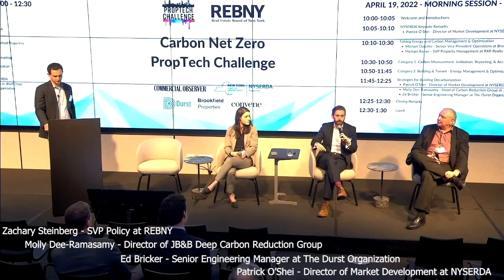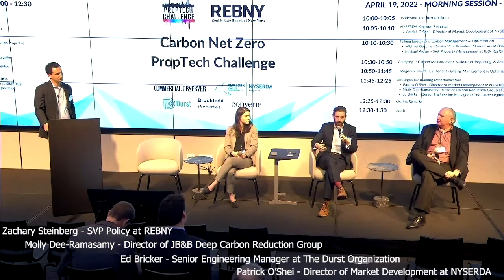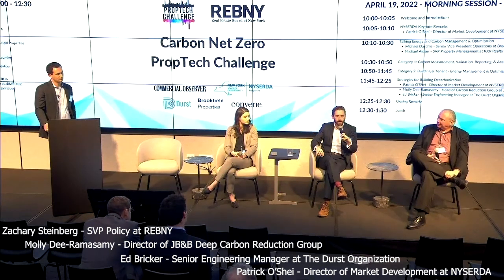We've made great use of utility submetering. When we did our renovation at the building next door, in this building at 151 West 42nd, we were actually able to downsize a lot of central plant equipment because we had BTU meters on the chilled water system for a year prior. There was originally something like 5,000 tons of chiller installed at the building. We cut that down to 4,000 because we realized the building only operates above 3,200 tons for maybe 3 or 4 hours a year. So we can ride through those kinds of hits.